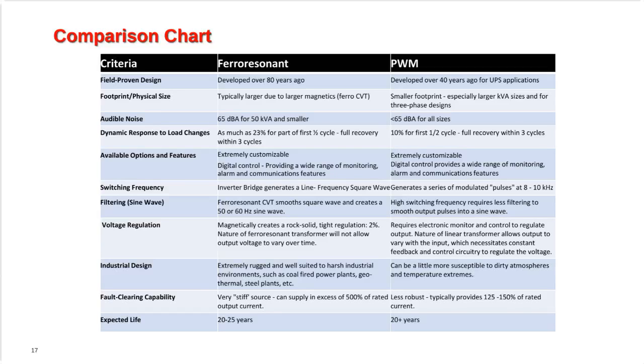What the PWM UPS is going to do is see the fault and transfer to bypass. The bypass supply, which is a very stiff source, will clear the fault. And then either through manual interaction, or if you have the auto transfer switch turned to the on position inside your UPS, it will transfer back to normal operation if the fault has been cleared. So PWM is not as robust, but it still will fulfill the needs of clearing faults by transferring to bypass.